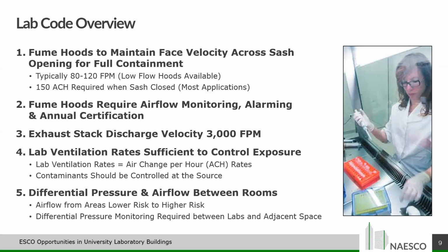And lastly, it's about lab differential pressure. The code says that airflow needs to go from areas of lower risk to areas of higher risk. What that means is, most labs are adjacent to a corridor, and you want air going from the corridor into the lab at all times. The reason's pretty obvious. You don't want any chemicals or smells in that lab getting distributed throughout the building. And you need to monitor that differential pressure so that if it ever reverses and your labs are positively pressurized compared to the corridor, it'll let the users know and immediate action can be taken. So that's not all the codes, but these are the ones that are really key when it comes to working inside of laboratories.